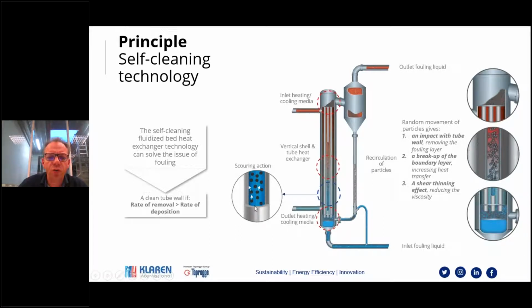And if you then would zoom into such a tube, you would see this fluidized bed of cleaning particles, where all the particles in a chaotic manner move inside the tube. And in this chaotic manner, they will impact each other, but they will also impact the tube wall. And it is these very light impacts that in fact give the scouring action of the particles and give the cleaning effect. And this is a light scouring action, meaning that the impact of the particles is capable to remove the development of a fouling layer, but it's not capable to erode the tube wall. So this fluidization, this impact, is in fact the mechanism behind the cleaning technology.